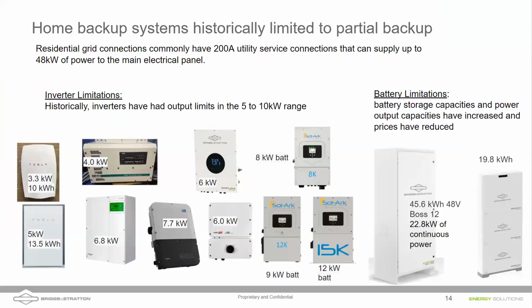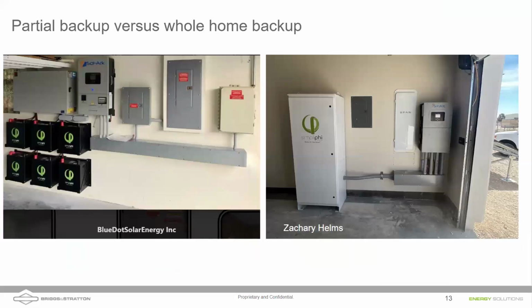One thing I wanted to point out, Nathan, if you go back a slide, is that notice the positioning of that Sol-Ark and the battery. They've positioned it in such a way in that garage that it's kind of near that wing wall where they not necessarily need to install a parking bollard, which is becoming more common with our inspectors, especially if that's a pre-tensioned concrete pad there. Last thing you want to do is start drilling into some rebar in there. So just wanted to point that out.